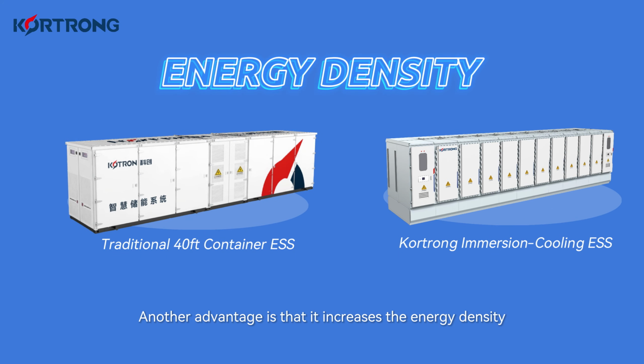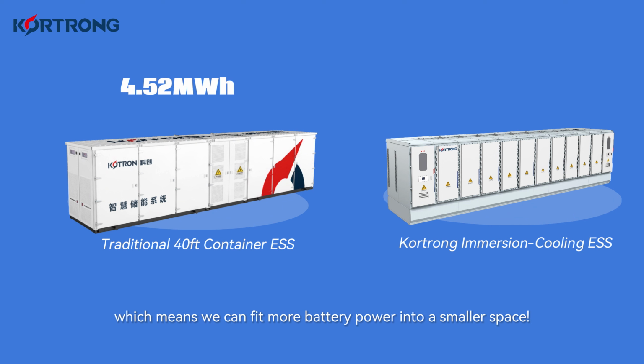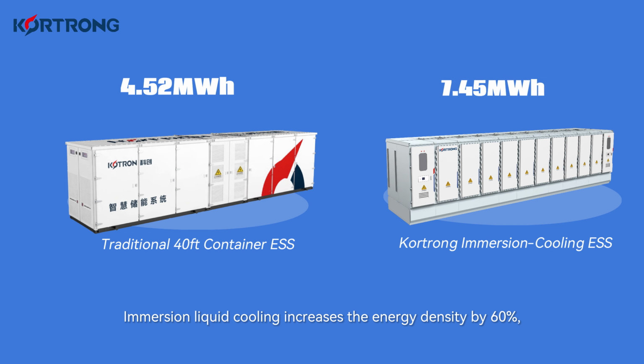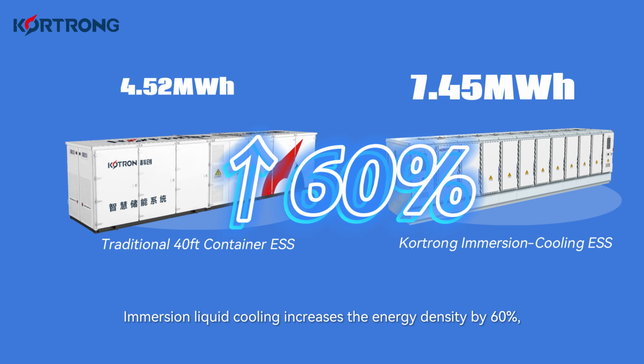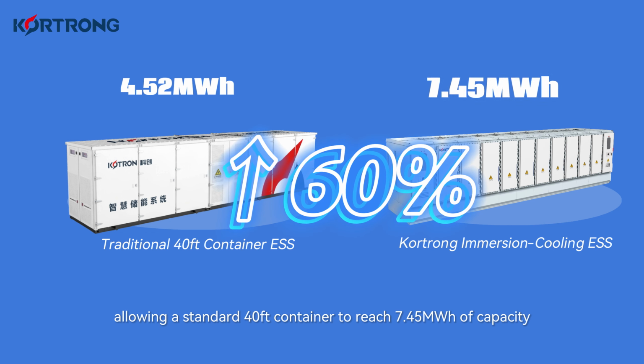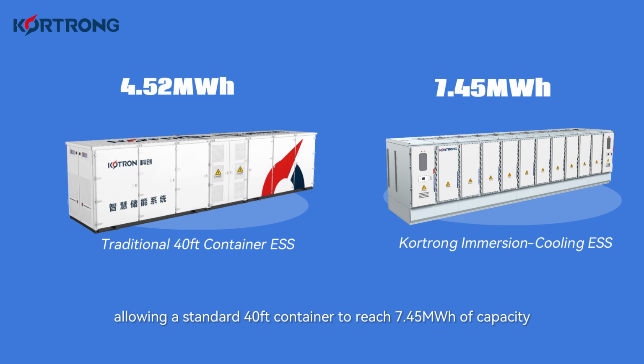Another advantage is that it increases the energy density, meaning we can fit more battery power into a smaller space. Immersion liquid cooling increases the energy density by 60%, allowing a standard 40-feet container to reach 7.45 megawatt-hours of capacity. Therefore, the investment costs can be lowered.